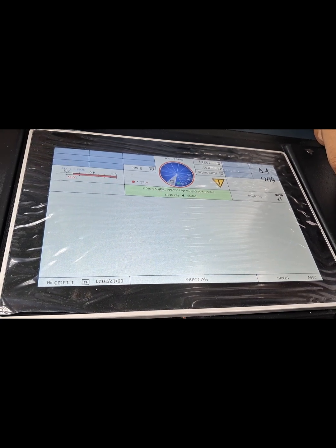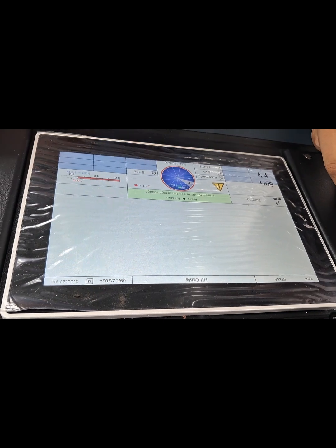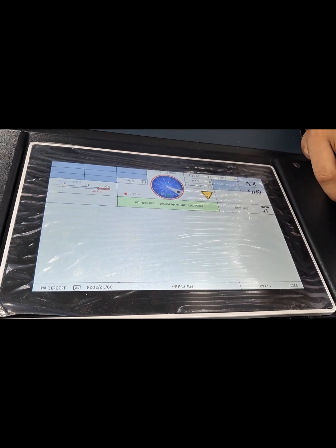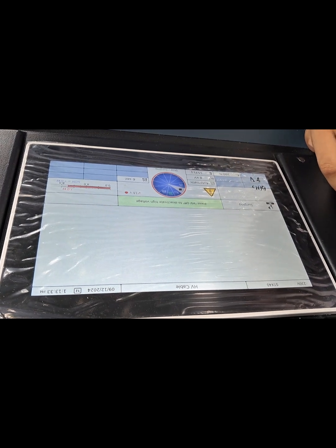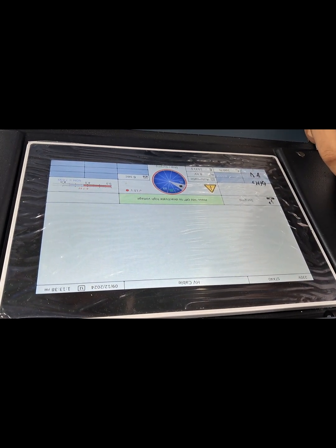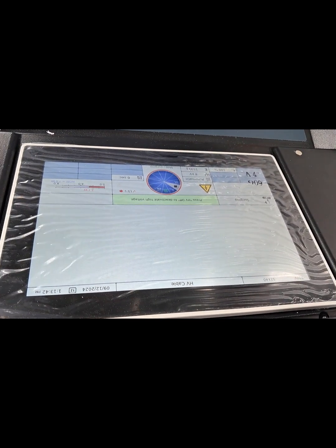You can select any time, from 3 to 10 seconds. Generally we follow 6 seconds. After 6 seconds, one surge will go. Now you have to take this instrument and feel where the fault point is.